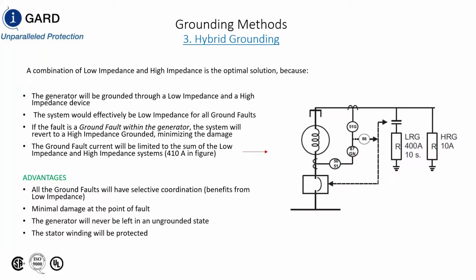And this comes into play with, I can give you an example, which is very simple. If you have fuse protection downstream and your largest fuse is 390 amps, you're not going to pick a 200 amp resistor and a 200 amp zigzag, because it might not be enough with the load that you have on the system to operate that fuse and clear the fault. And the danger in not clearing the fault is overheating the resistor to such a point where it becomes an open circuit and you'll never have a fault again.